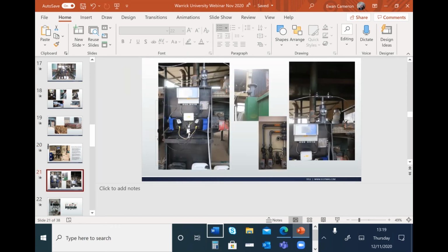And you can see here we have also added the ability to dose more than one tank from the same dosing unit. Instead of having, as we saw before, a tank on the left and a tank on the right, where we have to manually control which way it goes, we can now do that automatically with these solenoids. And again, you can pre-program that into your computer on this one here.